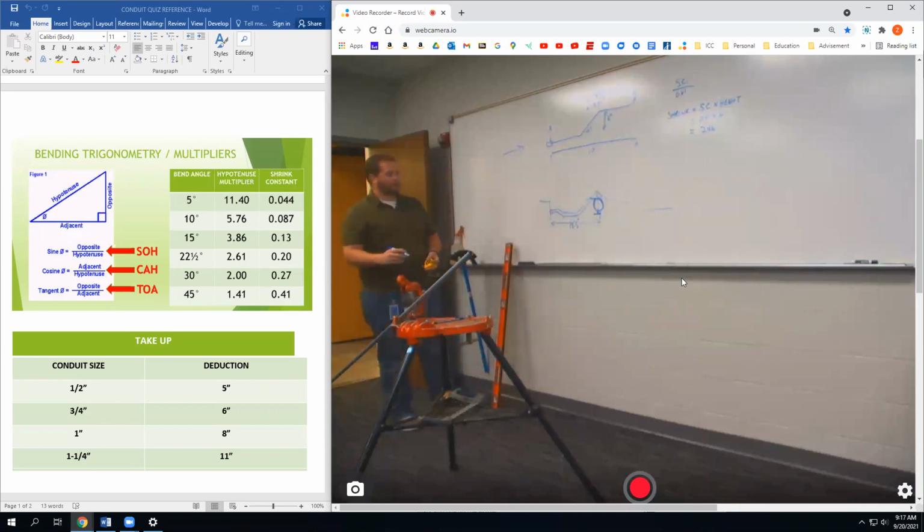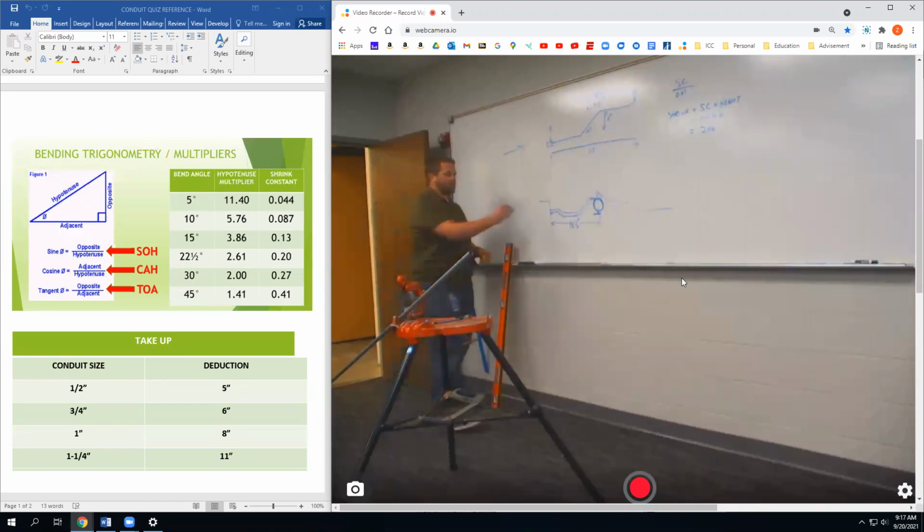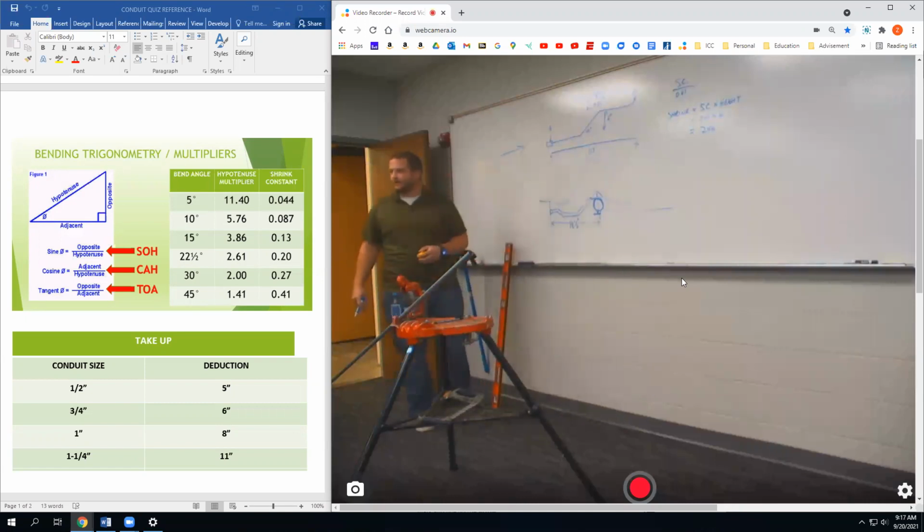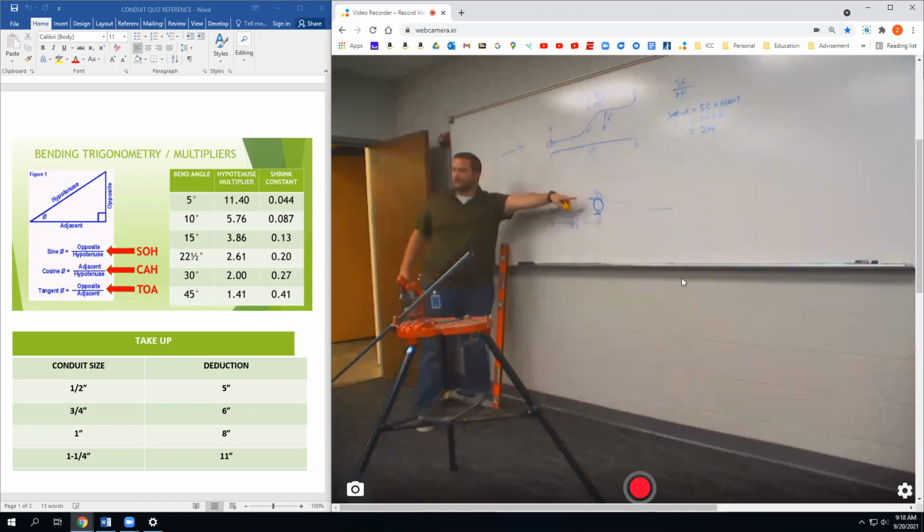When you're going over an obstruction like that, is it supposed to have clearance around the obstruction, or is it supposed to touch? It's all about looks. It's aesthetics. If you got a big old whoop, it looks bad. It doesn't look like you know what you're doing. If you hug it nice and tight around that pipe and keep going. The other thing is you don't want it cinched down on that pipe so hard that a plumber can't come through and take that pipe out without messing up your work.